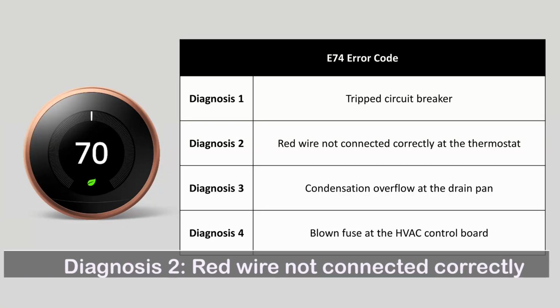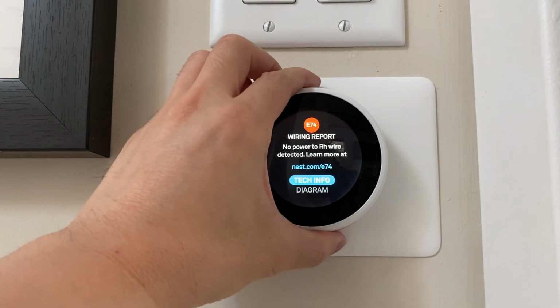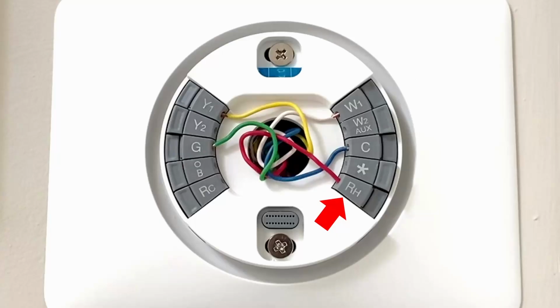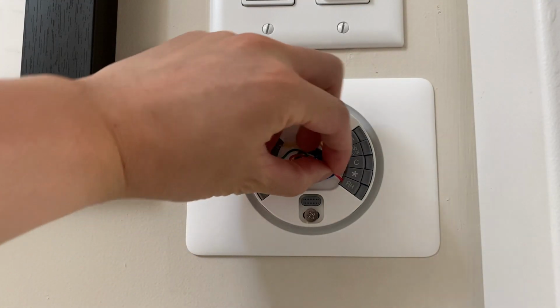Diagnosis 2. Red wire not connected correctly at the thermostat. Remove the thermostat display. Check the red wire is at the correct socket. Make sure the connector button stays down, and make sure the red wire is not loose.